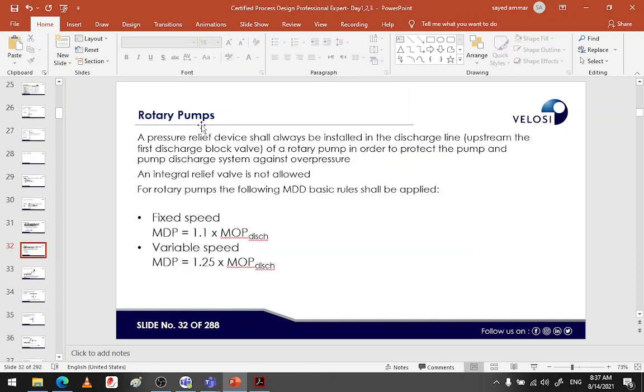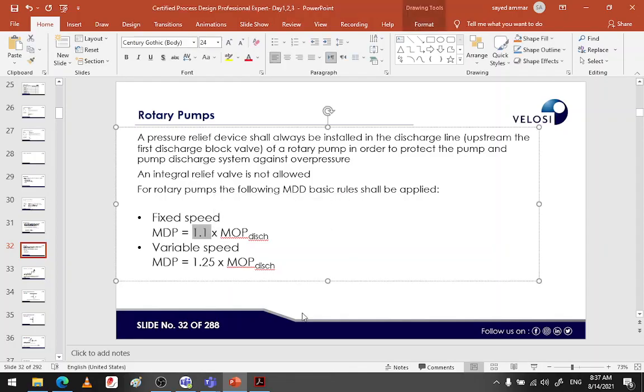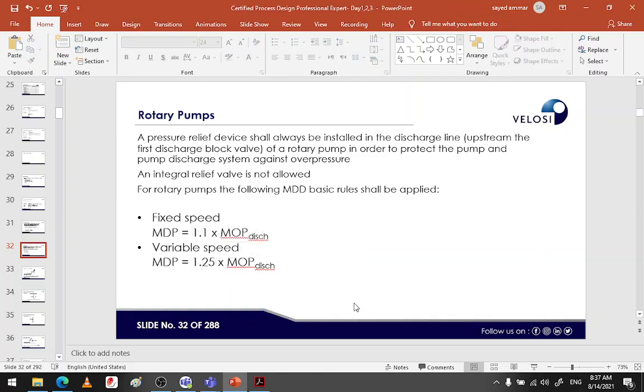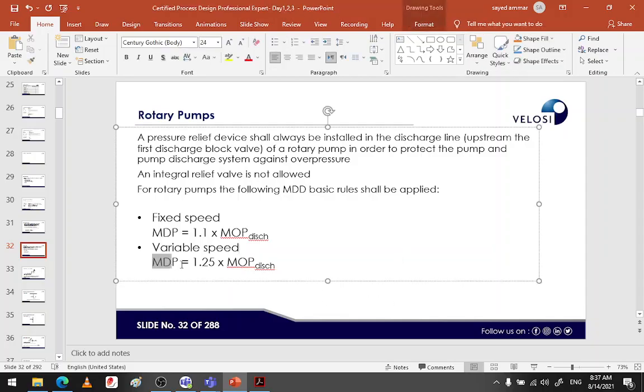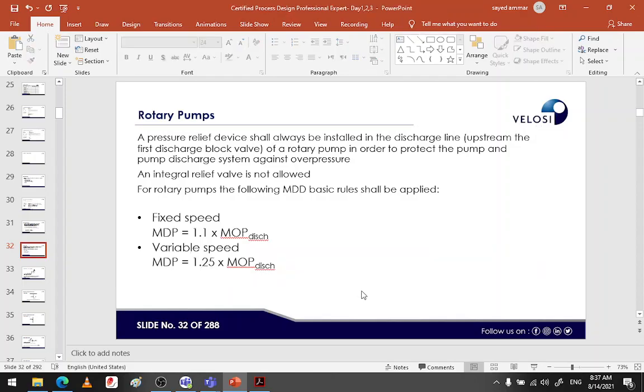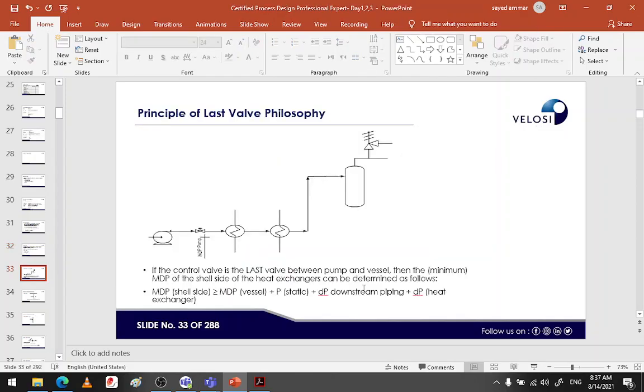And here are the rotary pumps, which will be 1.1 if it is fixed speed, and 1.25 maximum if it is variable speed. For me, if I am making a design, I stick with 1.25 to make sure that I am on the safe side. What is this?